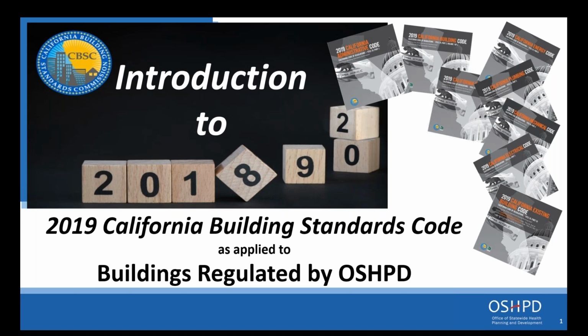When we're doing equipment replacements, you are allowed to replace equipment, and it is a project, but it should be equal to or similar in size. We're looking at weights, we're looking at anchorage. There's a lot of other factors involved with that. I think energy compliance here would be the least of your concerns, because the product itself is probably going to be already listed for sale in California.